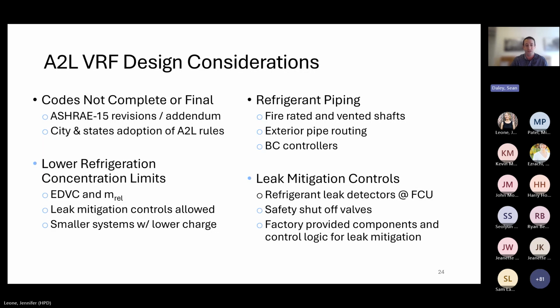Now they are allowing us to use leak mitigation controls, which I'm going to describe in a second. It helps us reduce the amount of refrigerant that would leak into a space. And finally, what are the lower refrigerant concentration limits going to result in moving forward? You're going to see smaller systems with lower refrigerant charges. As we continue VRF designs, the trend is going to turn towards smaller systems with lower charges, which makes it easier to comply with ASHRAE 15.